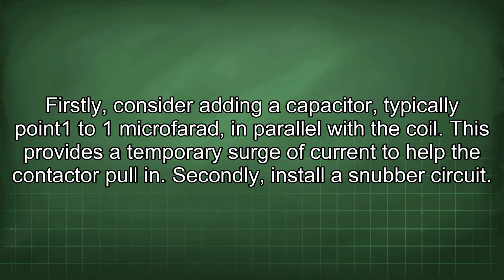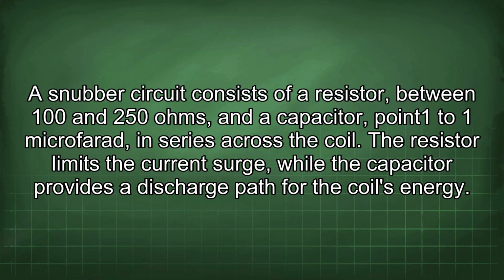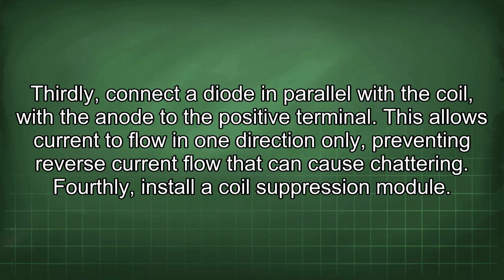Secondly, install a snubber circuit. A snubber circuit consists of a resistor between 100 and 250 ohms and a capacitor 0.1 to 1 microfarad in series across the coil. The resistor limits the current surge, while the capacitor provides a discharge path for the coil's energy. Thirdly, connect a diode in parallel with the coil with the anode to the positive terminal. This allows current to flow in one direction only, preventing reverse current flow that can cause chattering.